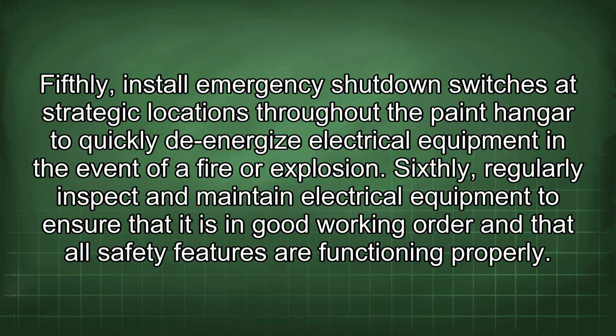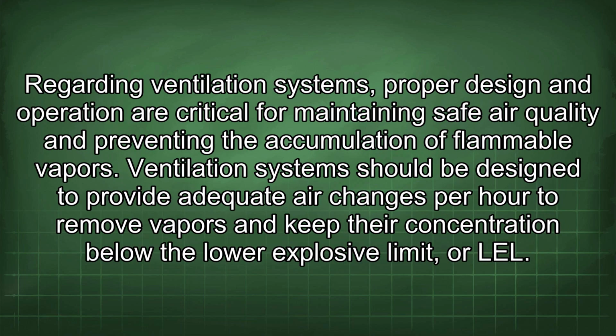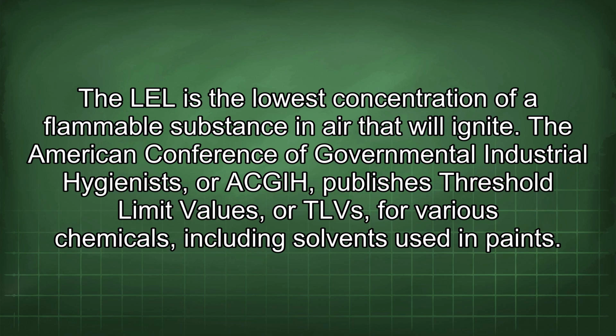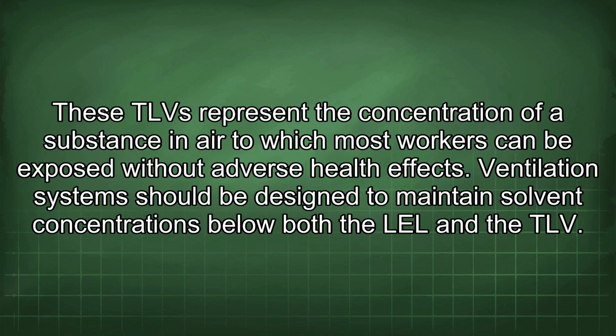Sixthly, regularly inspect and maintain electrical equipment to ensure that it is in good working order and that all safety features are functioning properly. Regarding ventilation systems, proper design and operation are critical for maintaining safe air quality and preventing the accumulation of flammable vapors. Ventilation systems should be designed to provide adequate air changes per hour to remove vapors and keep their concentration below the lower explosive limit, or LEL. The LEL is the lowest concentration of a flammable substance in air that will ignite. The American Conference of Governmental Industrial Hygienists, ACGIH, publishes threshold limit values, or TLVs, for various chemicals, including solvents used in paints. These TLVs represent the concentration of a substance in the air to which most workers can be exposed without adverse health effects. Ventilation systems should be designed to maintain solvent concentrations below both the LEL and the TLV.